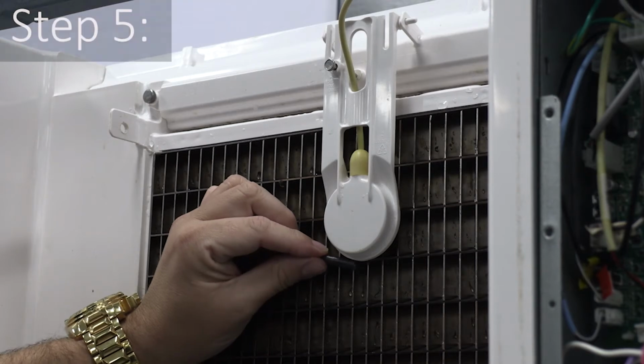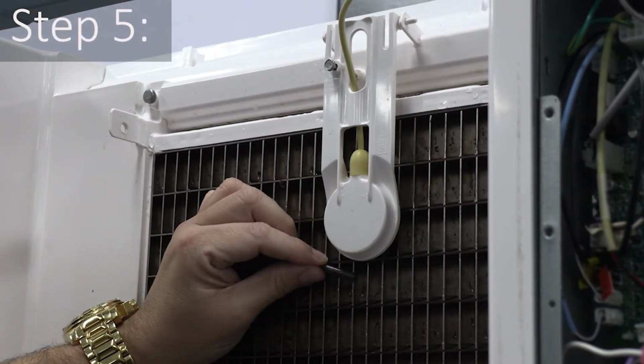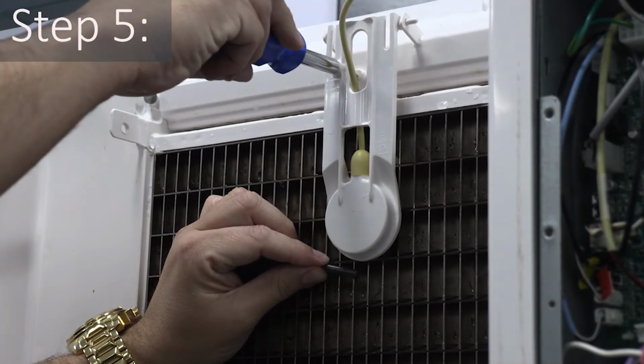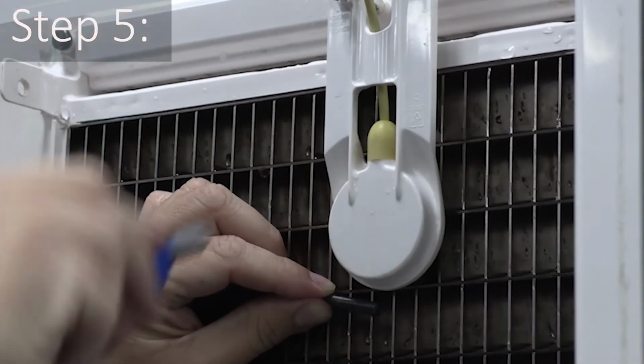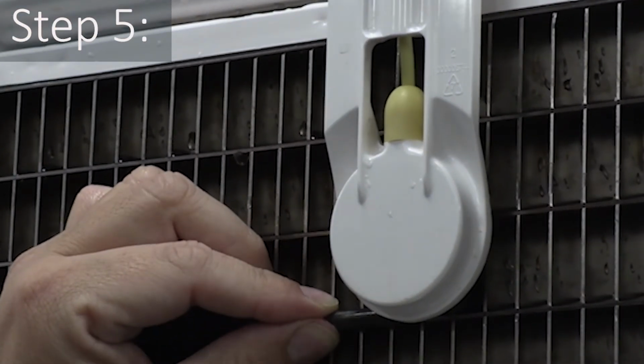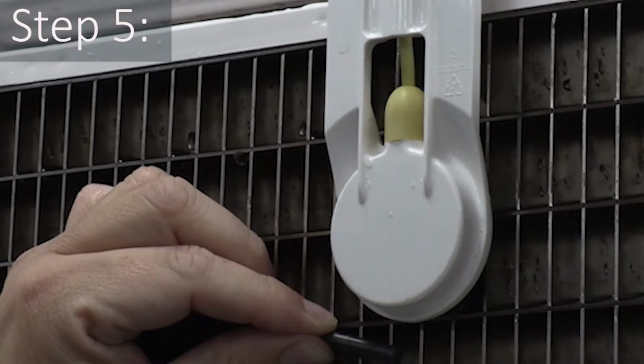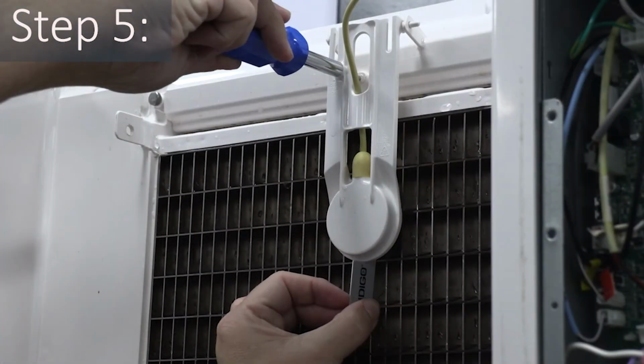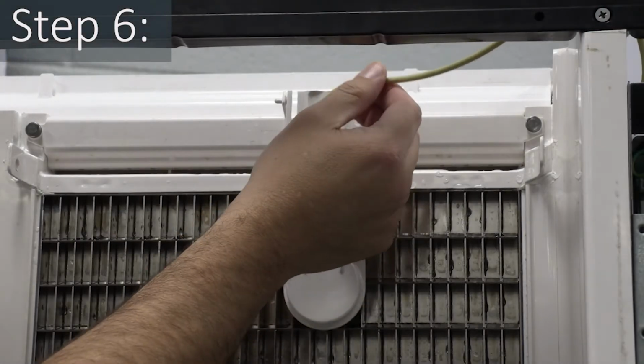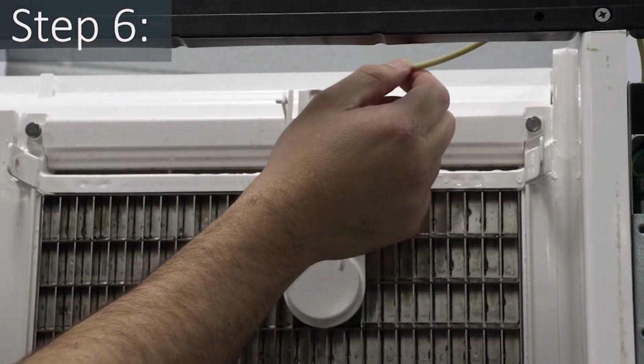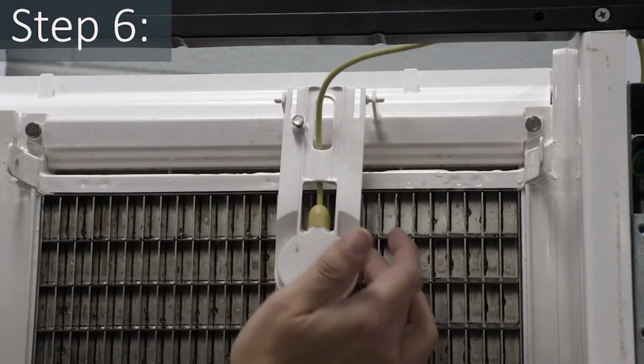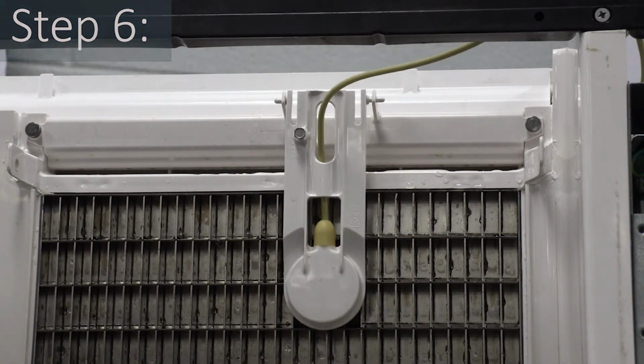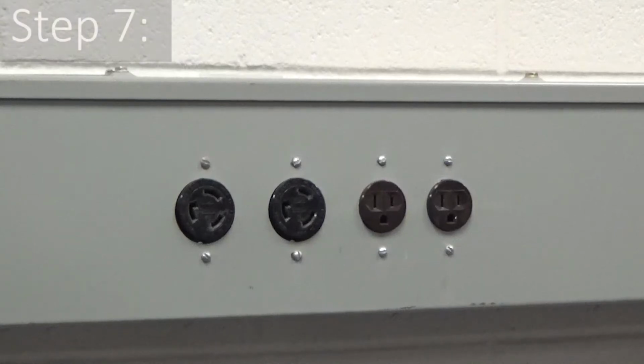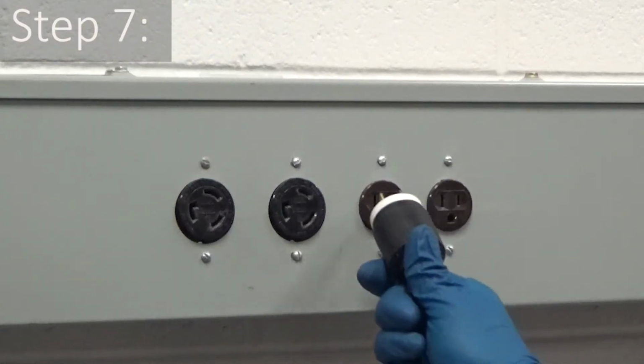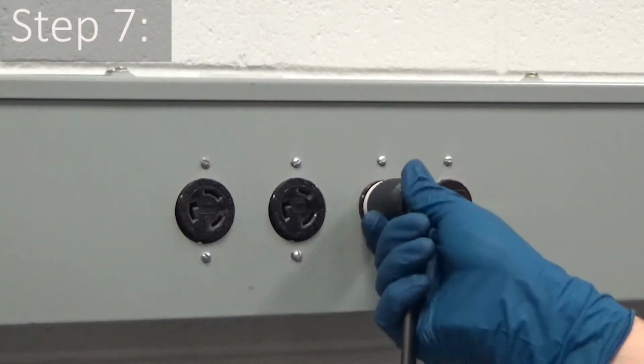Step 5. Verify proper ITP gap is at 9/32 of an inch or 7mm. We're using a sanitized drill bit, rolling it up the evaporator surface as a gauge to adjust the ITP. Step 6. Make sure the ice thickness probe wire and the bracket do not restrict the movement of the probe. Step 7. Reapply power to the ice machine and confirm the ice machine is in off mode.